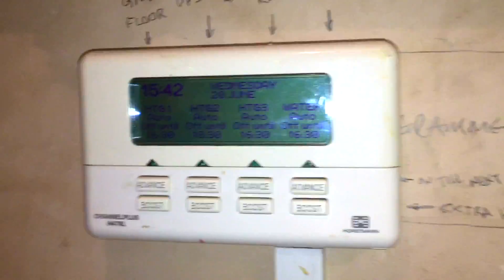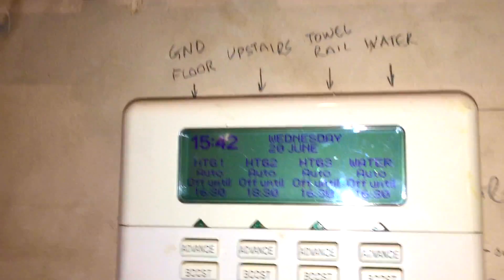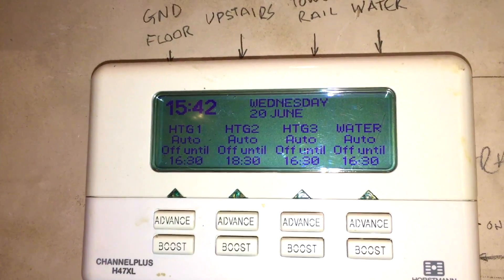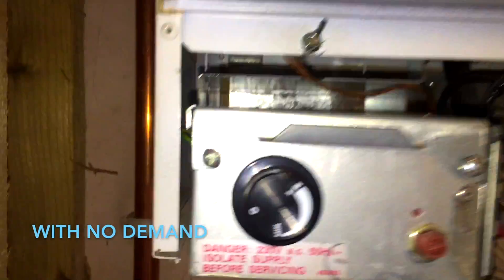There's a problem with the towel rails getting really hot and the hot water being way too hot. On arrival, the lady had the cover off, but she'd turned the power on. Everything here is off. The pump is running and the boiler was firing — I've just turned it off on the knob. We have four two-port valves on this system, labelled probably correctly.